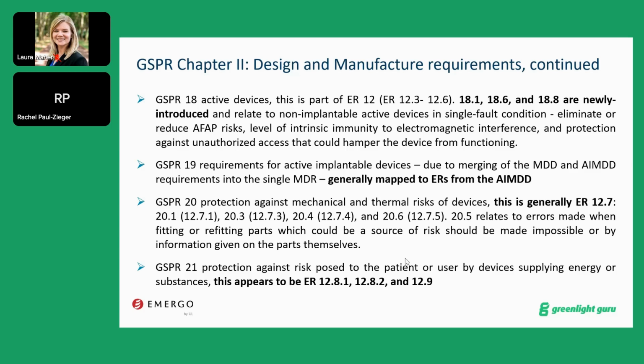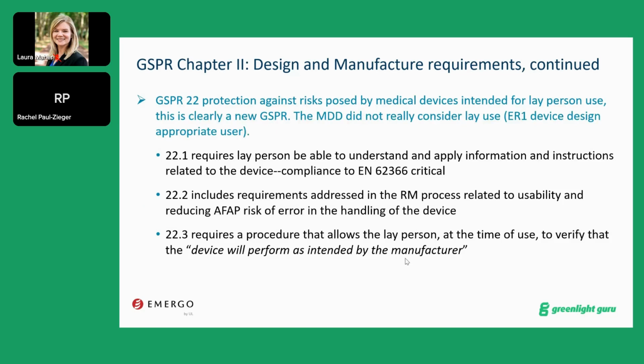GSPR 20, this is generally related to ER 12.7. And GSPR 21, this appears to be the ER 12.8 and 12.9. You have a new GSPR really focused on the protection against risk posed by medical device intended for layperson use.